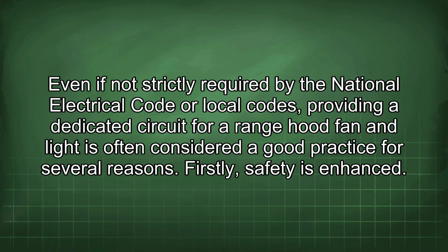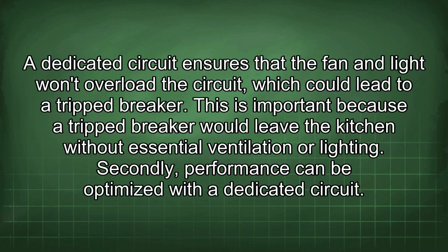Even if not strictly required by the National Electrical Code or local codes, providing a dedicated circuit for a range hood fan and light is often considered a good practice for several reasons. Firstly, safety is enhanced. A dedicated circuit ensures that the fan and light won't overload the circuit, which could lead to a tripped breaker. This is important because a tripped breaker would leave the kitchen without essential ventilation or lighting.